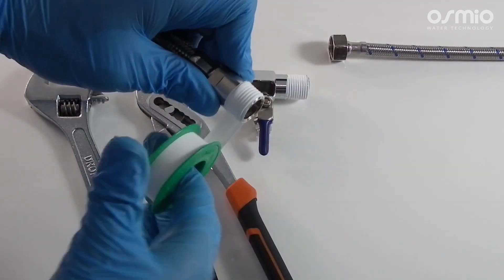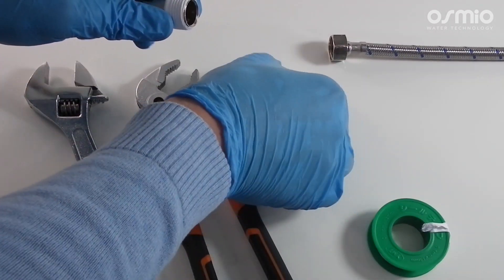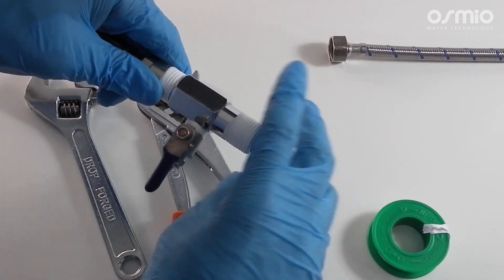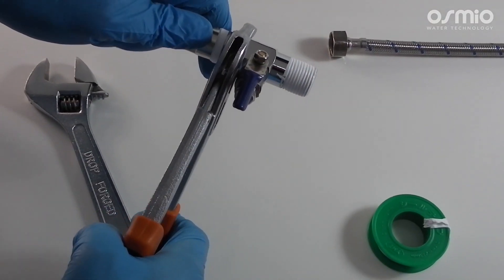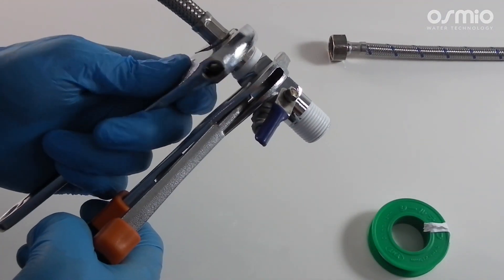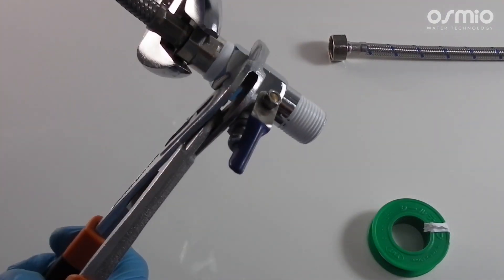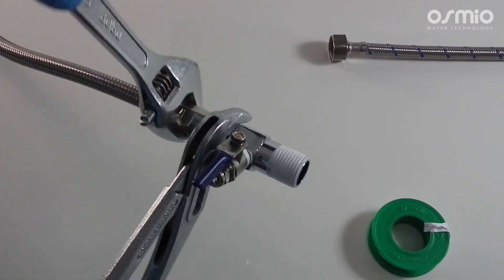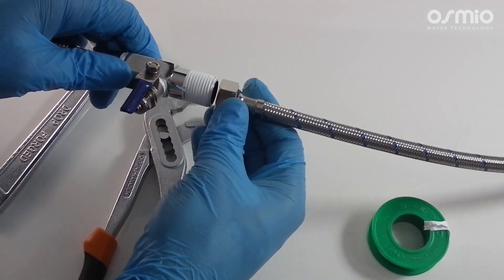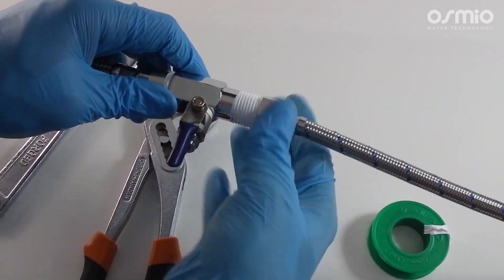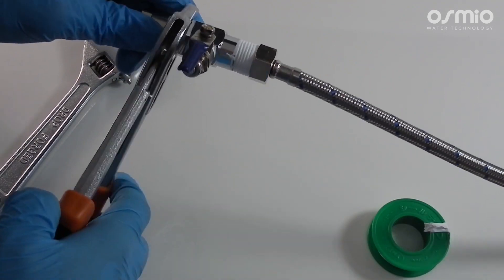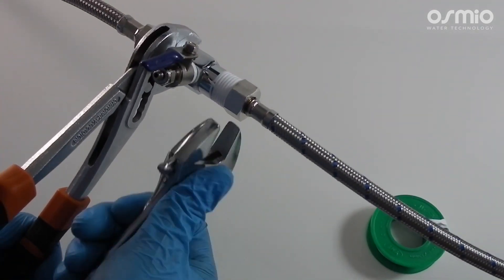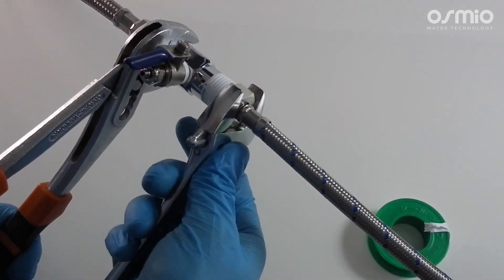Now we will fit the diverter valve between the main cold water feed, which normally has a 1/2 inch male thread connection, and the cold water line with 1/2 inch female thread to sink. Make sure to use PTFE tape on the male thread to make the connection watertight. You can use the spanner to support the diverter valve while tightening connections with a wrench.